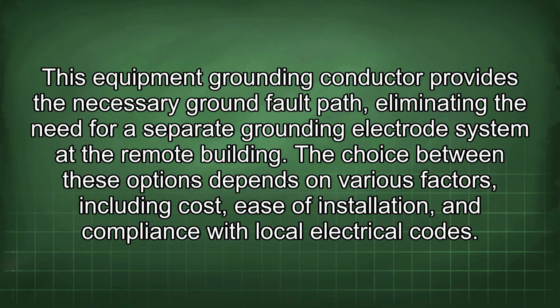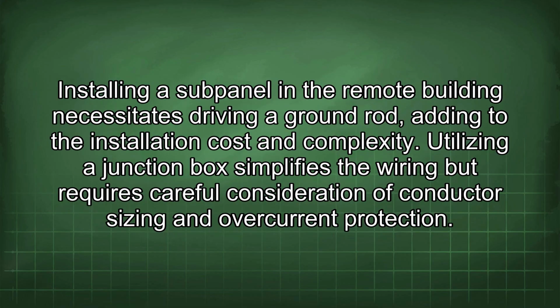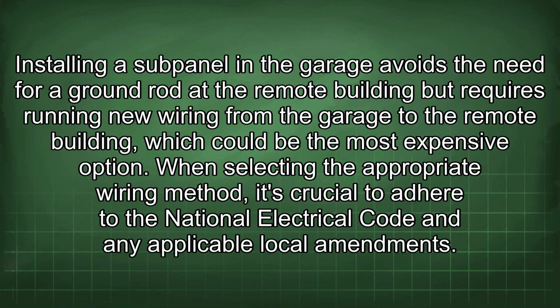the remote building. The choice between these options depends on various factors, including cost, ease of installation, and compliance with local electrical codes. Installing a subpanel in the remote building necessitates driving a ground rod, adding to the installation cost and complexity. Utilizing a junction box simplifies the wiring but requires careful consideration of conductor sizing and overcurrent protection. Installing a subpanel in the garage avoids the need for a ground rod at the remote building but requires running new wiring from the garage to the remote building, which could be the most expensive option.